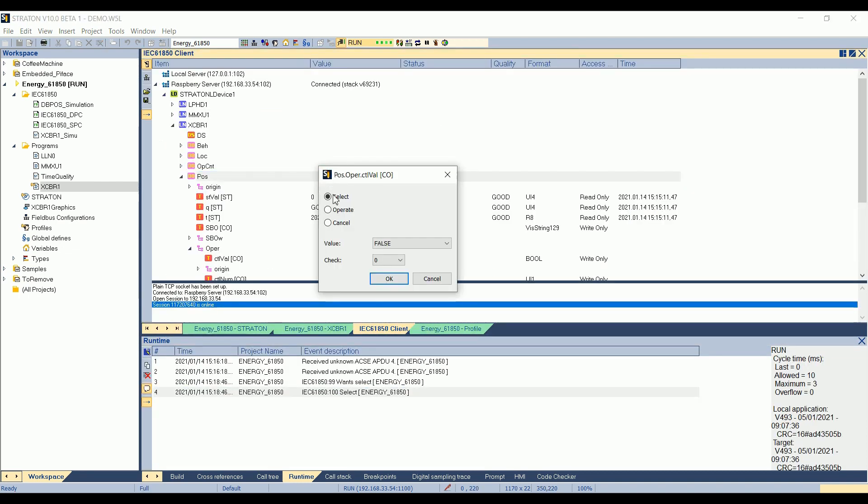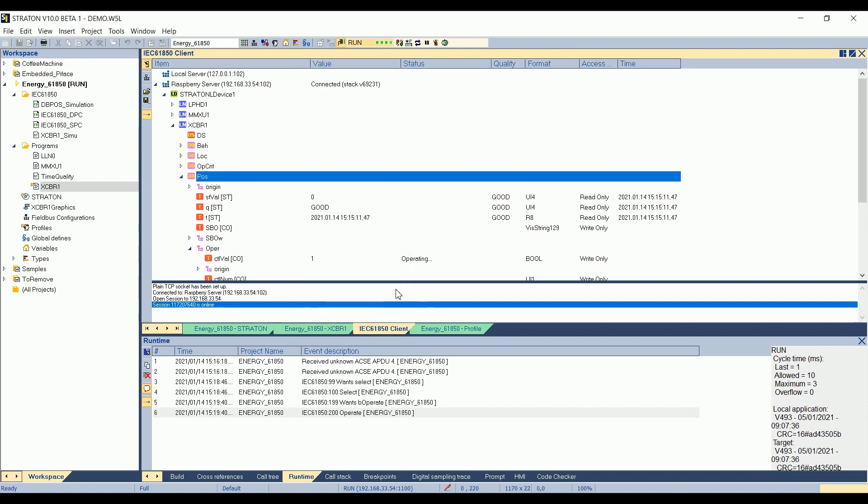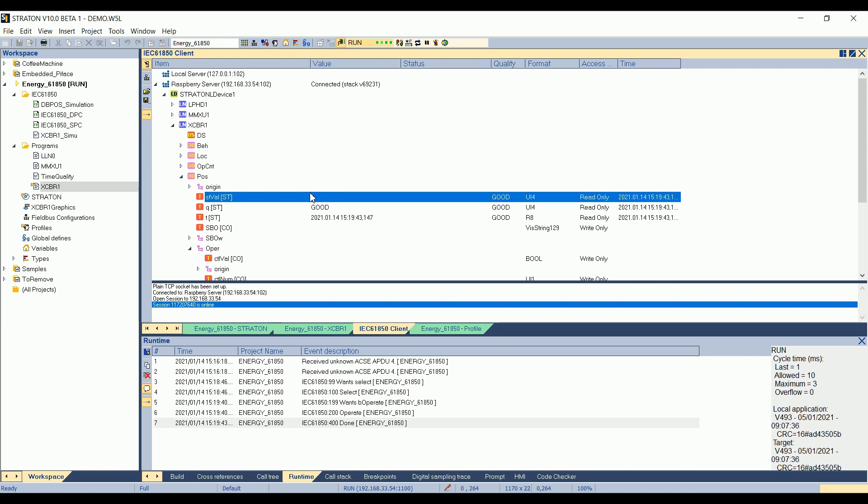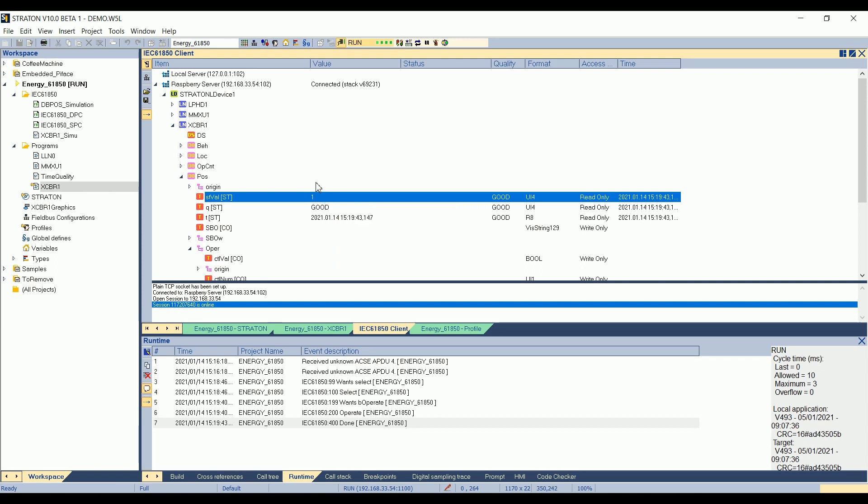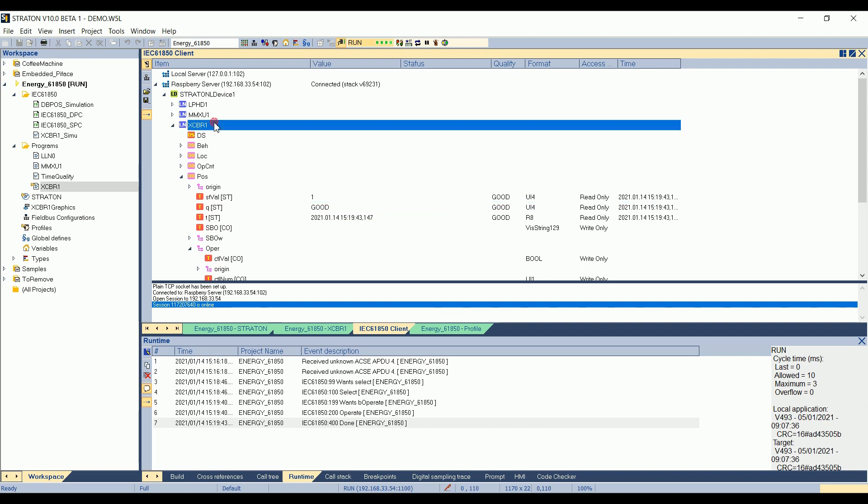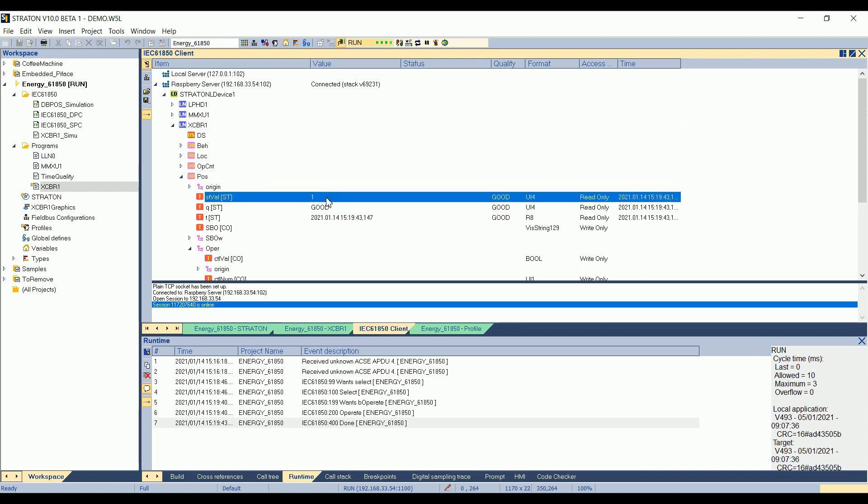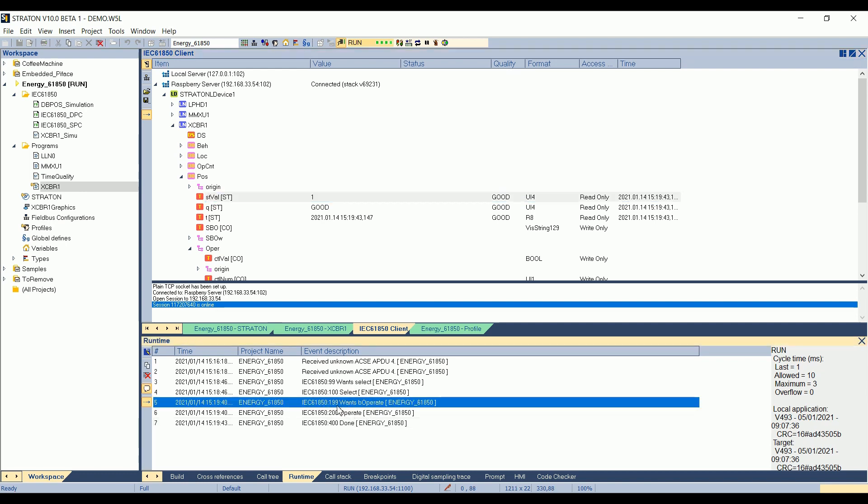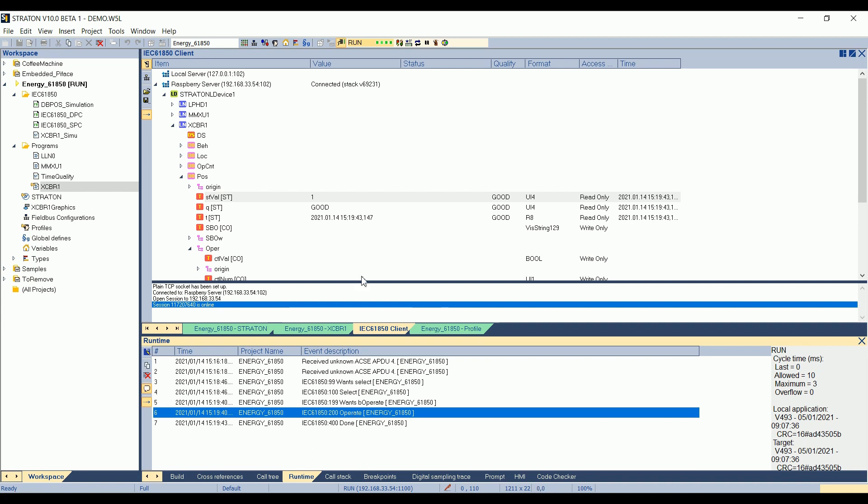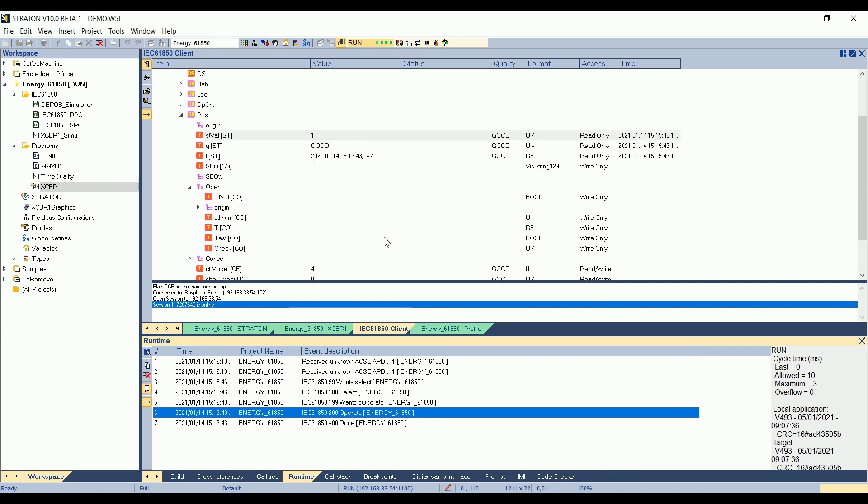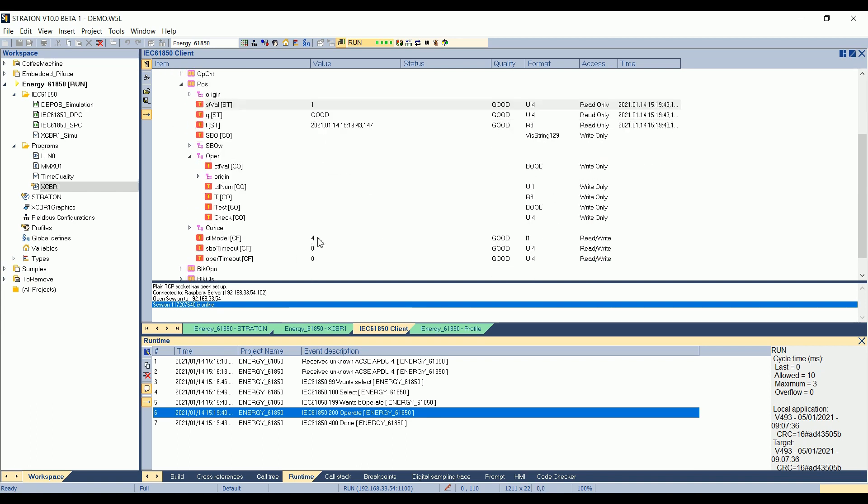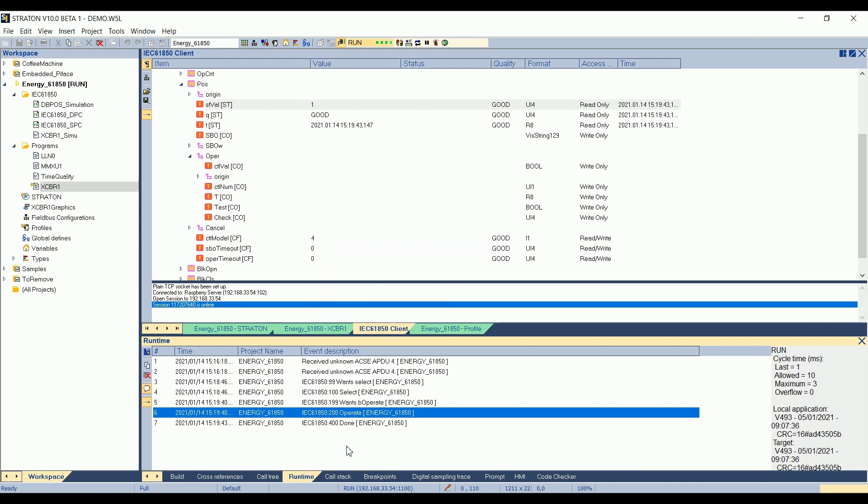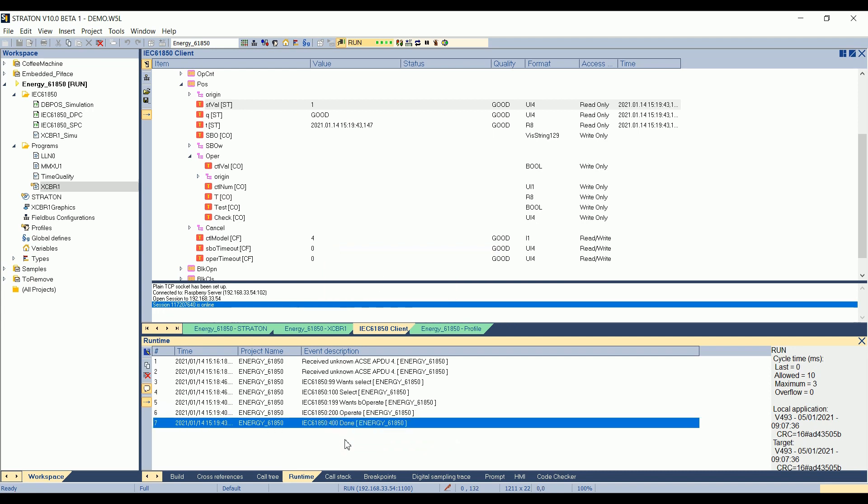Now I go back on the client. I double-click on the position. I say that I want to do an operate to true. I click on OK. The server receives the operate. The STVAL is changing to 2, for a moment, indicating an intermediate position. And then to 1, indicating that now the circuit breaker position has been set to 1. On the runtime output, I can see that it received a want to operate. The operate has been accepted. And as I am in Control Model 4, which is select before operate with enhanced security, also, the operation has been validated here via the control variable, which is 400. So the operation has been done.